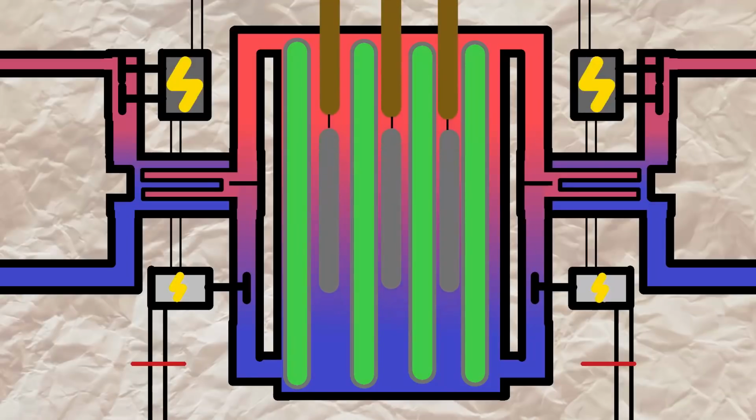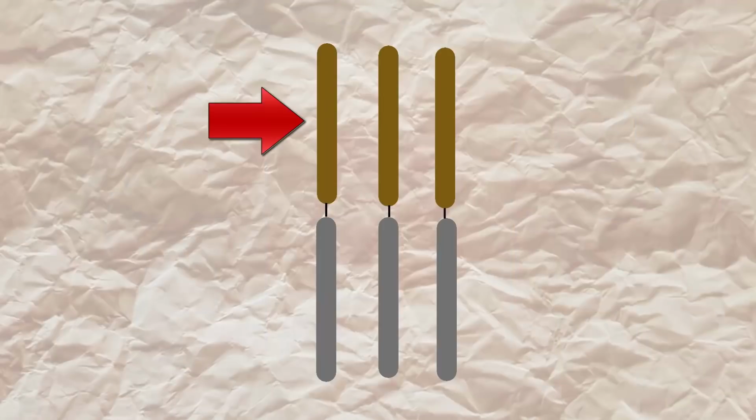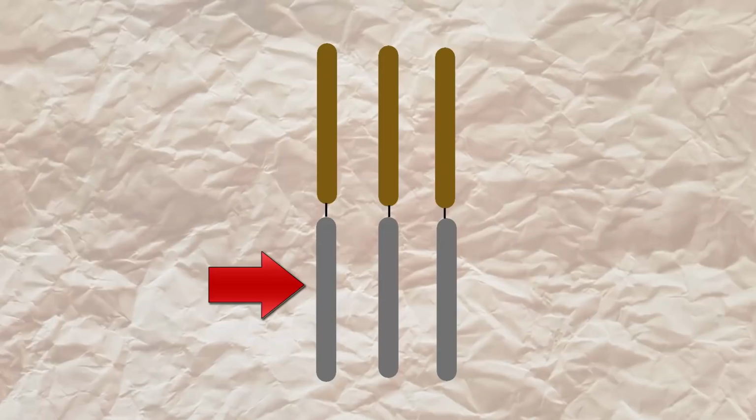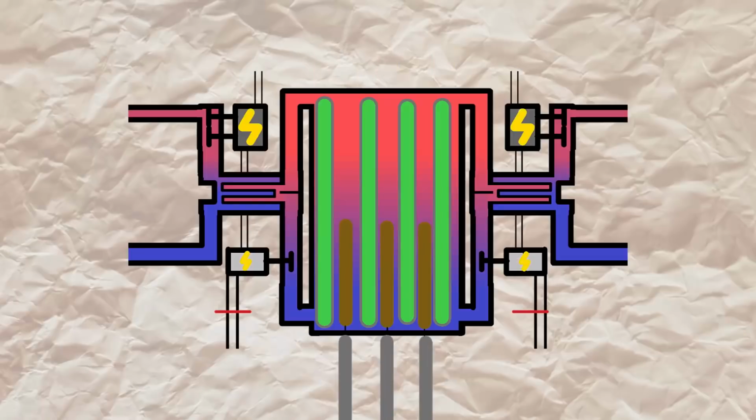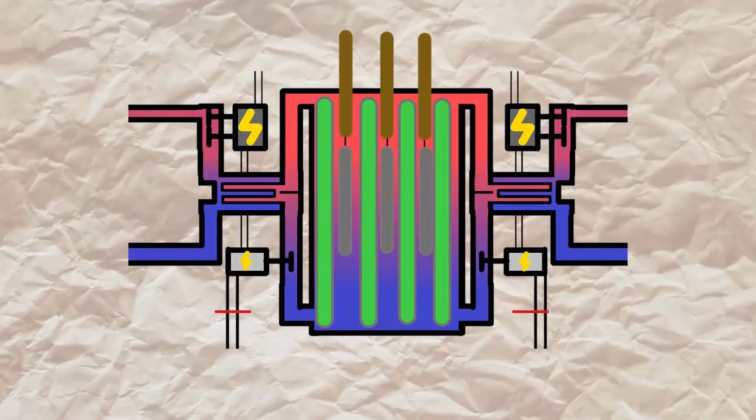Thing about those control rods, they are mainly boron, but attached to them, on the bottom, there are rods made of graphite. Boron stops neutrons, graphite makes them able to fission. The logic is that when you take the boron out of the reactor, you probably want to increase the power. So the graphite is there to help you with that. But they withdrew the rods completely, including the graphite.